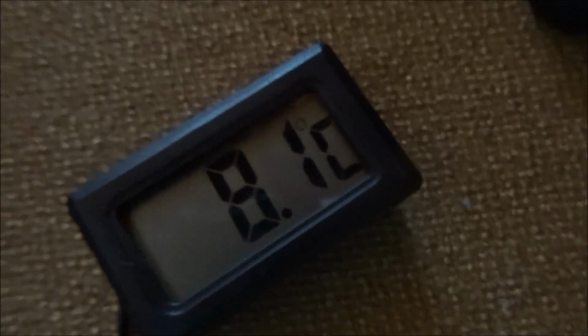The more air, the more refrigerant pressure, and the more refrigerant pressure, the higher the temperature of the lines, or the refrigerant temperature, actually goes up, the more airflow you got in the evaporator. So that means a little bit higher temperature, but again, 8.1 degrees. That's 46.58 degrees Fahrenheit. Now we're gonna check the return temperature and the intake air temperature from outside.